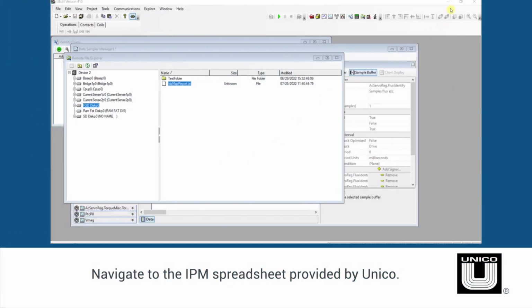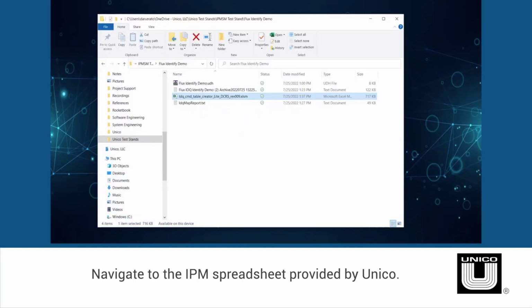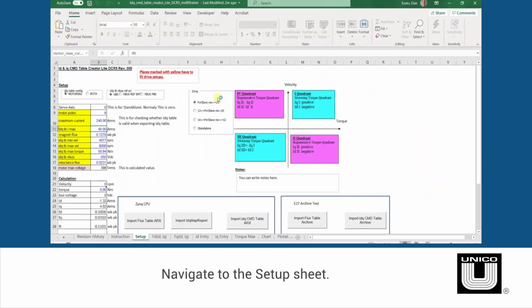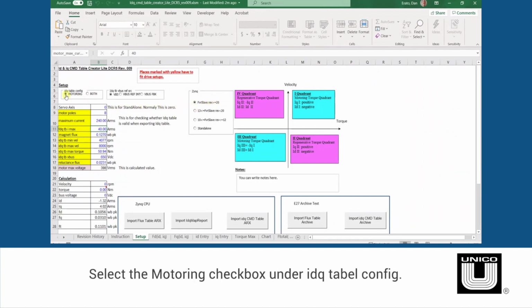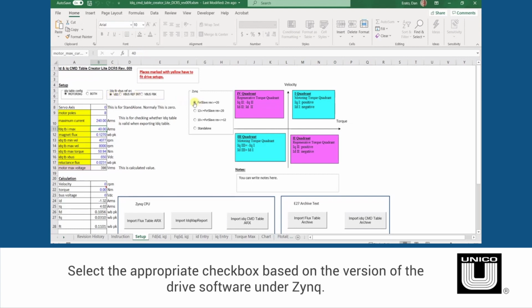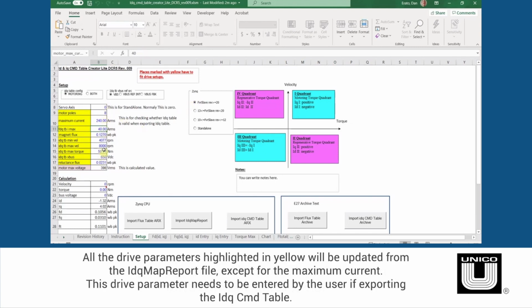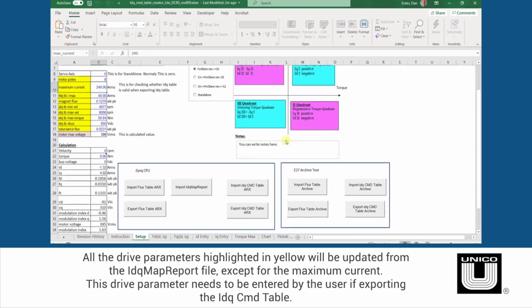The next step is to analyze the data using the IPM spreadsheet provided by Unico. In the IPM spreadsheet, navigate to the Setup sheet. Since only a motoring flux map was generated, select the motoring checkbox. Then select the VBus checkbox for bus voltage. Lastly, select the appropriate checkbox based on the version of the drive software. All the drive parameters highlighted in yellow will be updated from the IDQ map report file, except the maximum current.